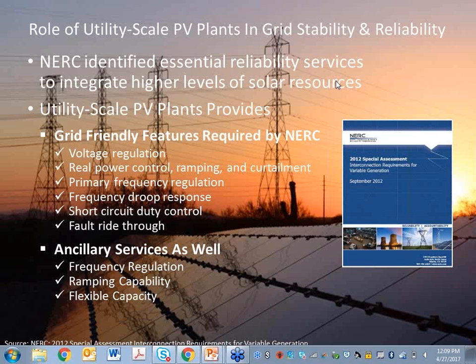Have you tested the system in islanded mode? No, because this is a utility scale PV plant, and to operate in islanded mode you need grid-forming inverters and a local load. That wasn't the purpose of this plant—it's a commercial utility scale plant, so it's not physically possible to do it. But there are other projects at smaller scale looking at PV as an energy supplier in a microgrid, done in many places in the U.S. and the world. That's a subject of a different area of work.